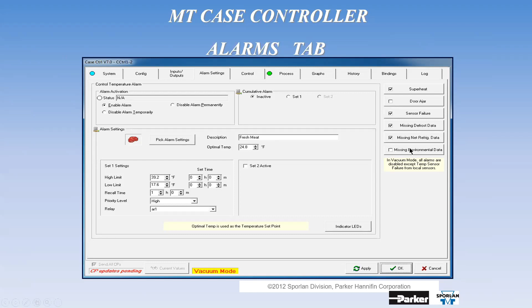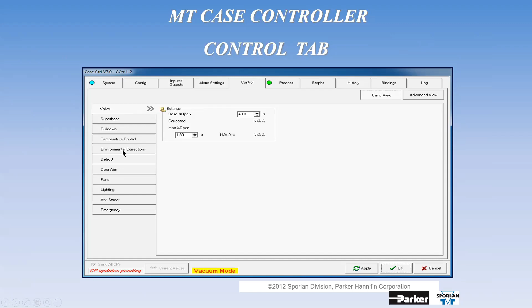Here's my control tab. Now look at this. Inside the control tab, I have a valve, a superheat, a pull down, a temperature control, an environmental, defrost. I have set points or algorithms for that type of control. This all gets to this. This is the takeaway of what all that means, and that's an awful lot to throw at you. But if you're going to use MicroThermo case controllers, and we want you to use them, we want you to get your money's worth. This green line here, that's the actual temperature. You can't see the blue line behind it, but take my word for it, that's the set point. It's hardly visible because my actual operating temperature is right above it.